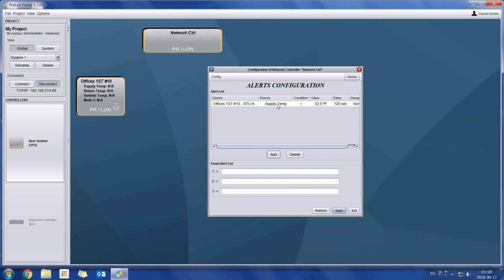Then we have the source here. So we can double click on this and we'll have a drop down list of all of the points of the controller. So all the inputs and outputs are here. And so we can choose any of these points which we want to monitor. So let's say we want to look at the supply temperature. We can set the condition, so whether it gets smaller or larger than. So I could say if the supply temperature gets colder than 42 degrees for a certain delay, so the default delay is 2 minutes. So if the supply temperature is colder than 42 degrees for 2 minutes, then we can send off an email alert up to 3 different addresses.